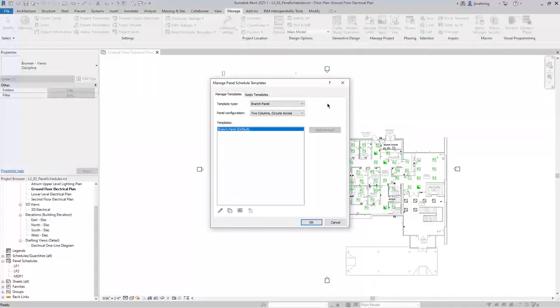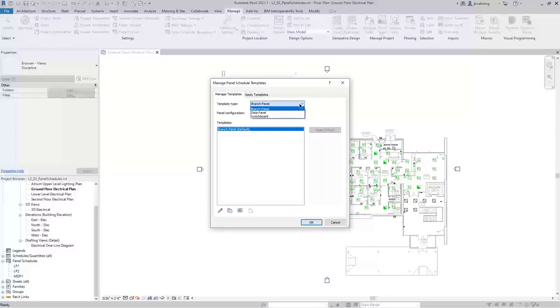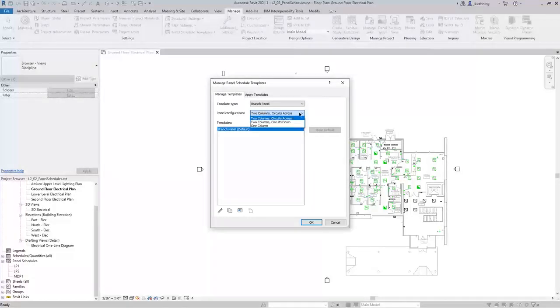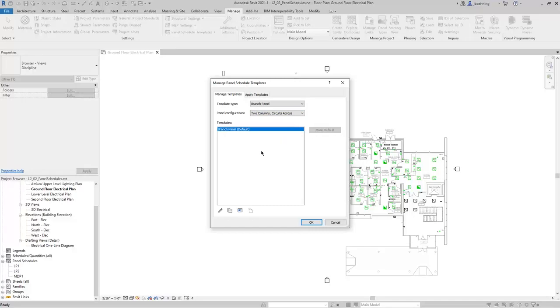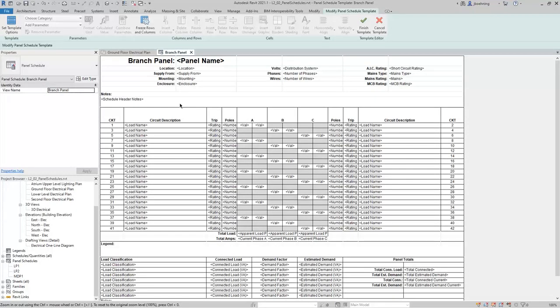In this dialog, there are two tabs: Manage Templates and Apply Templates. We'll begin on the Manage Templates tab. You can select a template type, which can be Branch Panel, Data Panel, or Switchboard. With Branch Panel selected, you can then choose one of the panel configurations. You can create panel schedule templates for each template type, and for Branch Panels, you can create templates for each panel configuration. I'll select two columns, Circuits Across. With the template selected, you can click Edit, and Revit goes into Modify Panel Schedule Template mode.